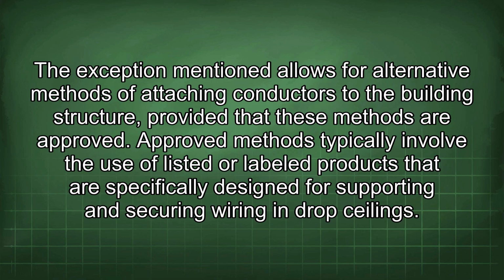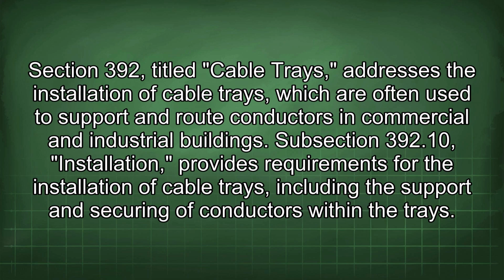Approved methods typically involve the use of listed or labeled products that are specifically designed for supporting and securing wiring in drop ceilings. Section 392, titled Cable Trays, addresses the installation of cable trays, which are often used to support and route conductors in commercial and industrial buildings. Subsection 392.10 Installation provides requirements for the installation of cable trays, including the support and securing of conductors within the trays.